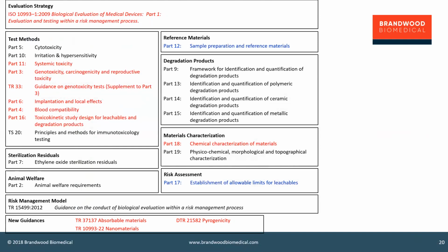So the evaluation needs to be applied to the finished device. So that is the device which has been processed, where the starting materials have been turned into a printed part. That part has been subject to post-processing. It may have been polished, it may have been cleaned, it may have had further machining steps. It has then been packaged and then sterilized. And it's that bit, the device that's been through all of that, that actually needs to be evaluated for biocompatibility.